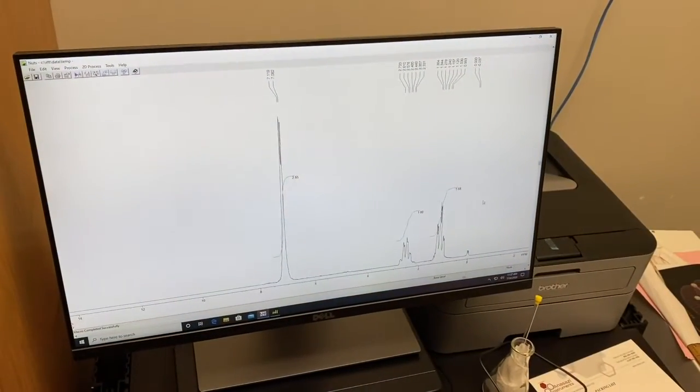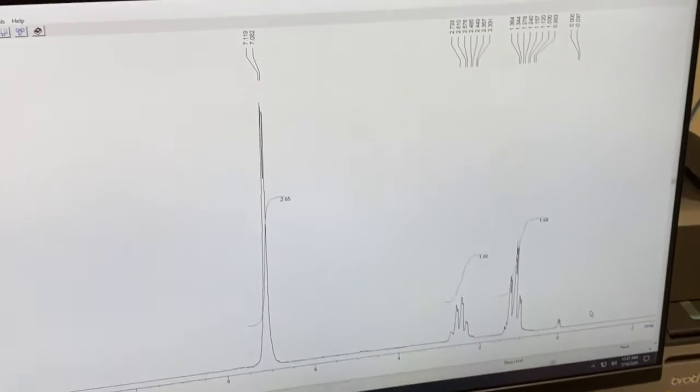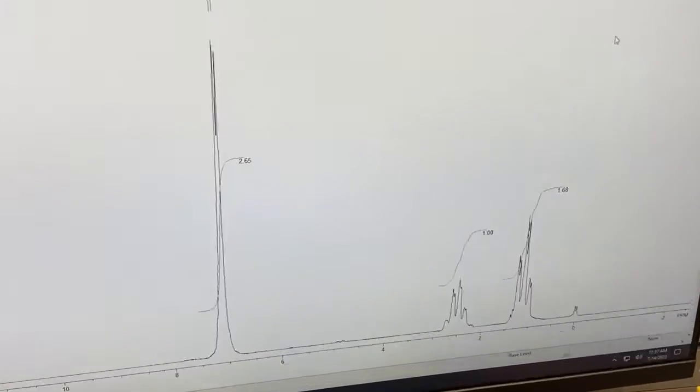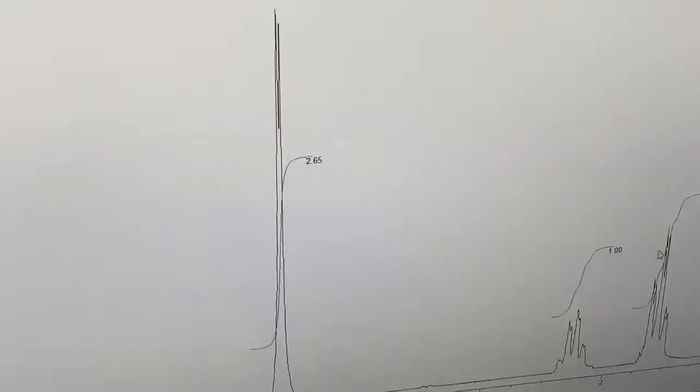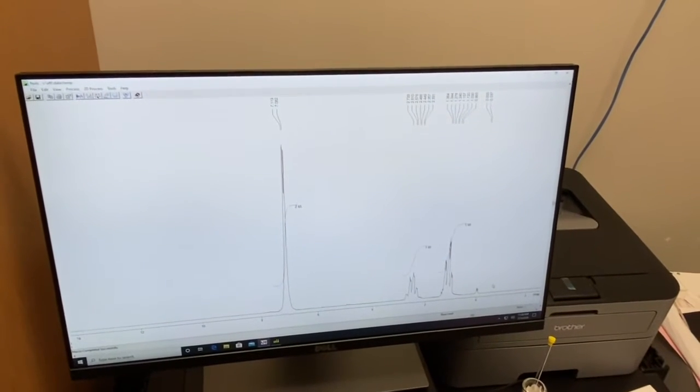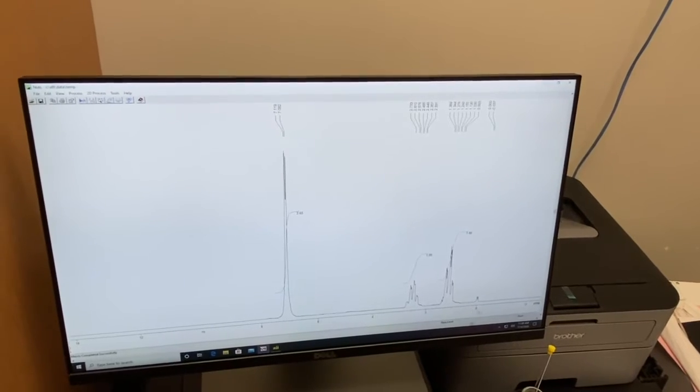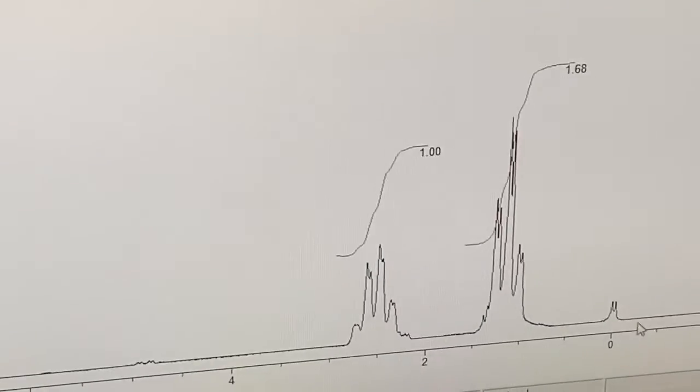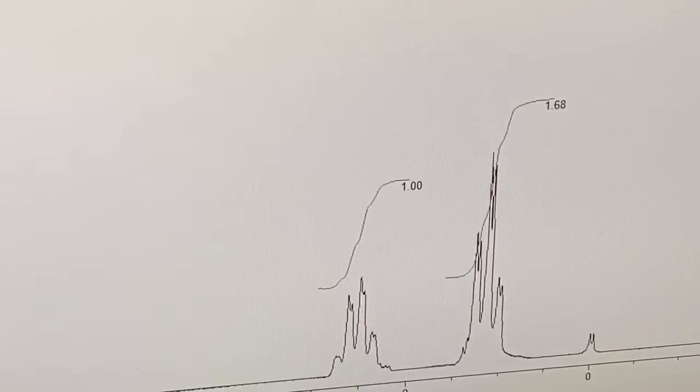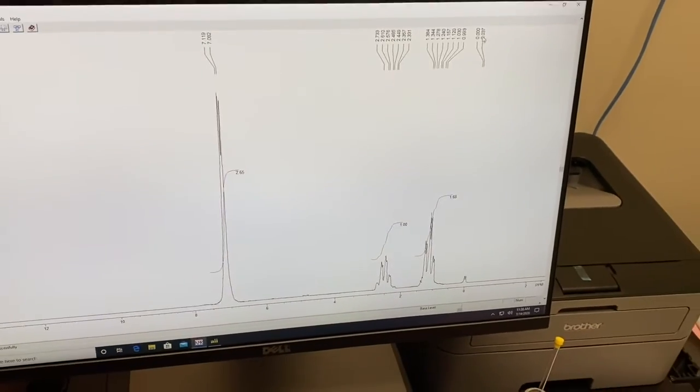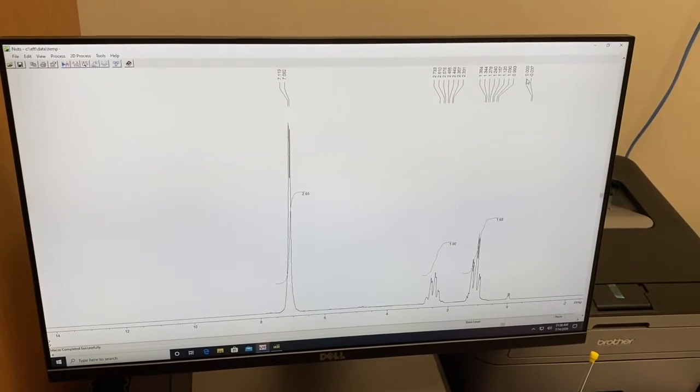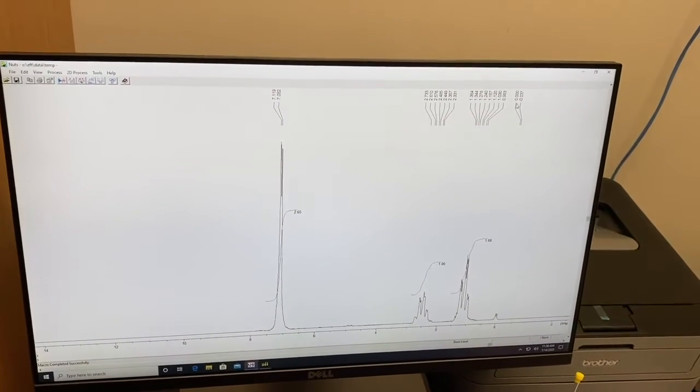And you can see that it has some peak labels on it. They're at the top of the peaks. They tell you the chemical shift or parts per million value. And you can also see some integrations. We have some adjusting to do though. The first thing you'll want to pay attention to and verify is that TMS is set to zero, which it always should be. So come to the furthest right-hand peak. Locate TMS. We see that it's at zero, so we're fine. If it's not, the directions lead you through a few short commands to change that scale and shift it to zero. You want to do that first.